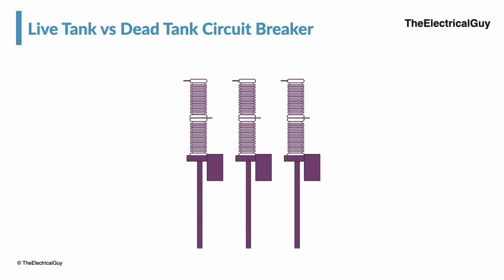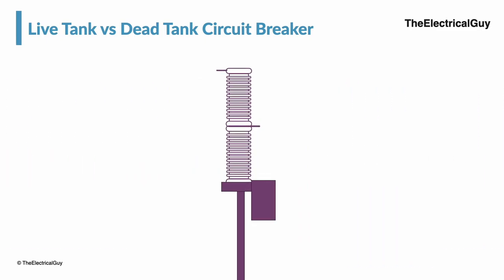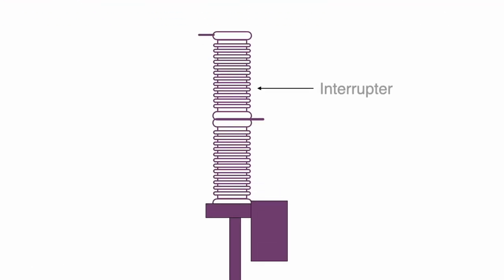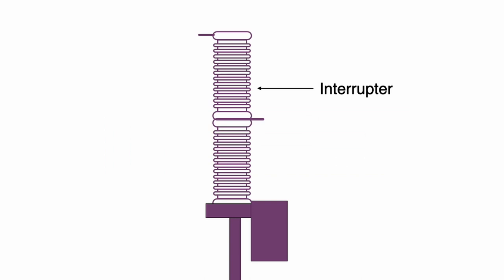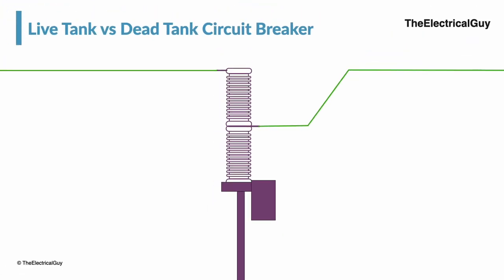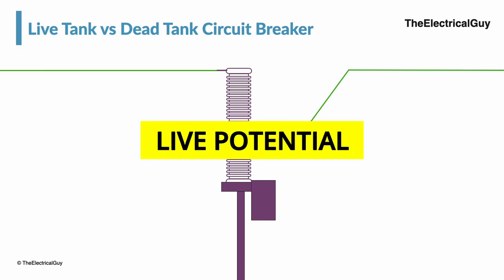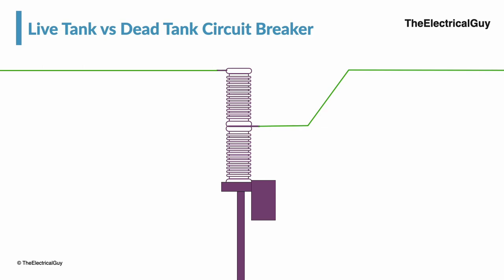Now look at the circuit breaker shown on the screen. For better understanding, I am only showing a single phase of the 3-phase circuit breaker. The top part consists of the interrupter — inside the top insulator, fixed and moving main and arcing contacts are there. The insulator can be made of porcelain or silicon composite material. To the interrupter part we connect the incoming and outgoing supply, and as a result the interrupter part is at a high or live potential. Hence such breakers are called live tank circuit breakers.